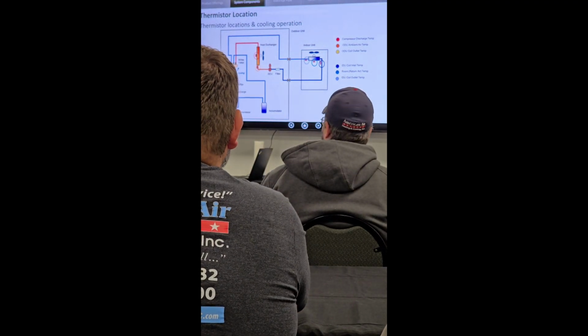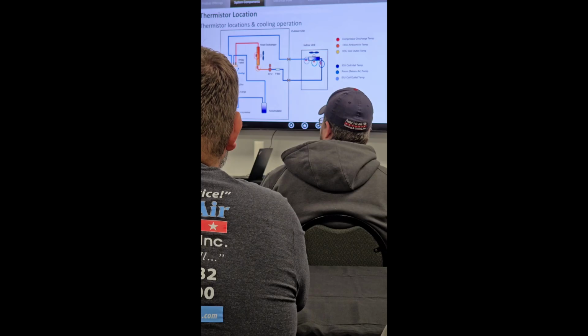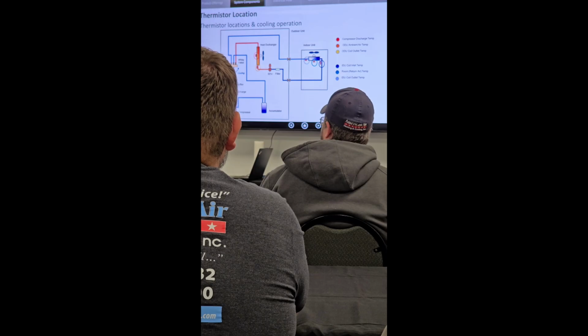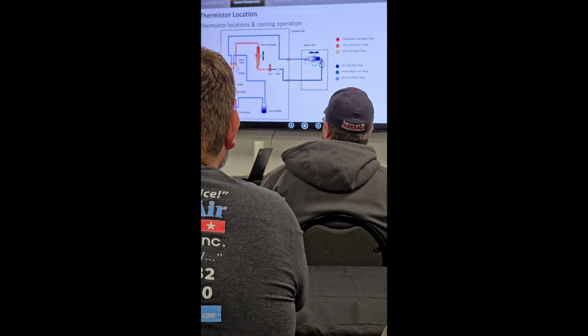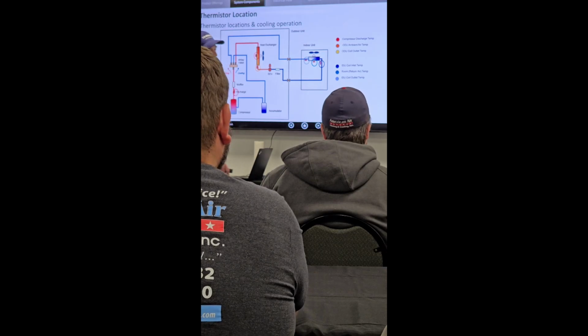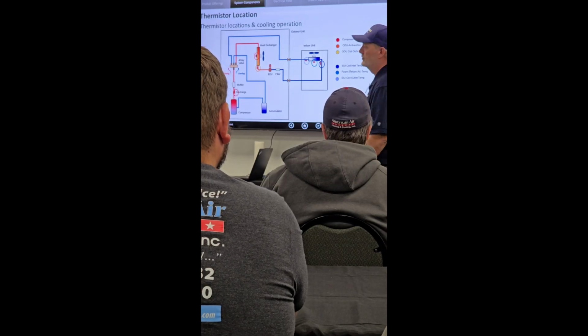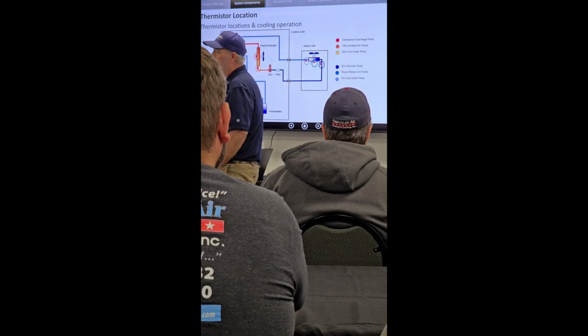One more question: I know they vibrate a little bit. If it's a flare fit and not soldered in, isn't that loop supposed to be a vibration loop? If you torqued it right, it shouldn't vibrate. No, I haven't seen our line sets vibrate from that standpoint, because if you look at this condenser, these base valves are basically bolted in place. The only thing making that line set move, honestly, is the movement of the refrigerant.